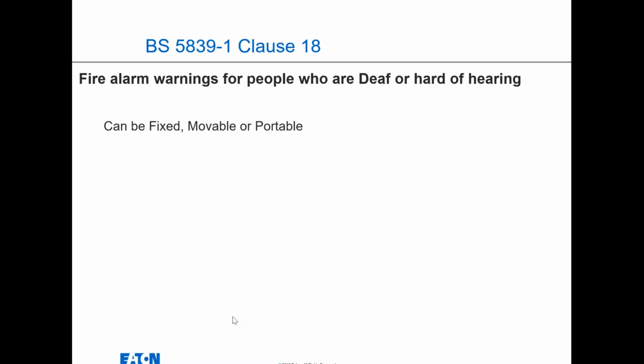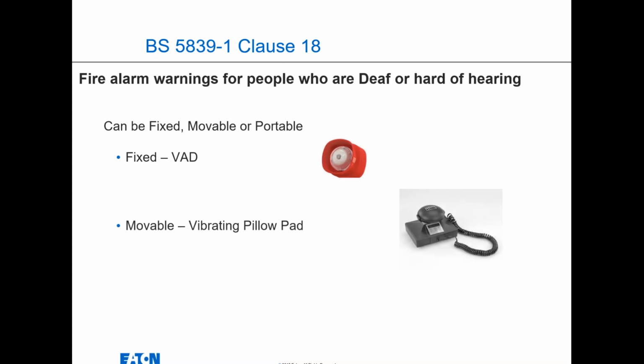Strange. So fixed warnings for people who are deaf or hard of hearing. There can be many different types and the interfaces that go with those for the fire alarm system. So you have got deaf alerters, which are pagers that they can carry around with them. Those need to be considered, but they have to be compliant as well. And obviously the critical path is making sure that that person gets that fire signal just as if the fire alarm has gone off with sound pressure levels. We also talked about VADs, vibrating pillow pads and pagers.